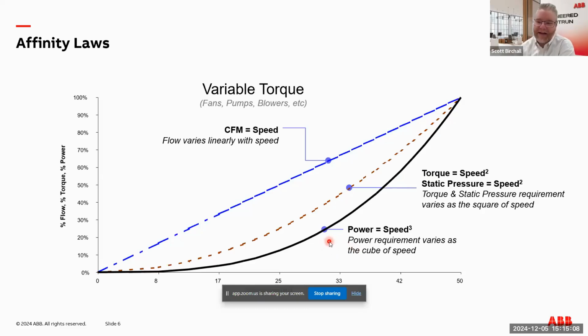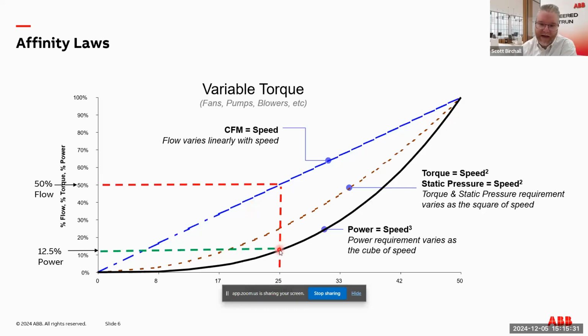So let's take a look at an example here. At full speed, 50 hertz, I'd be at 100% power and 100% airflow. But my system's oversized. I don't need it for the day. So my system says, you know what? I'm good at half flow right now. So let's take a look at that. At half flow, which is this point right here, if I go down and follow this down to my power, I'm only at 12.5% power. So considerable energy savings by being able to slow things down, and it's a cube of the speed.